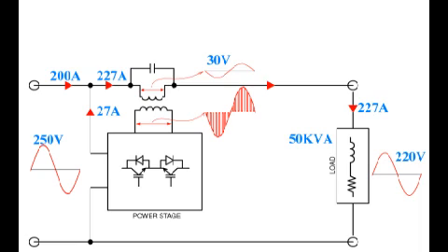This is the operation in buck mode. The input voltage is high at 250 V, so the PWM is generated in the opposite phase — 180 degrees out of phase with the input — and the voltage is subtracted from the input, giving a constant 220 V output. The input current is only 200 A because the voltage is 250 V, and 27 A flows back through the mains from the IGBT.